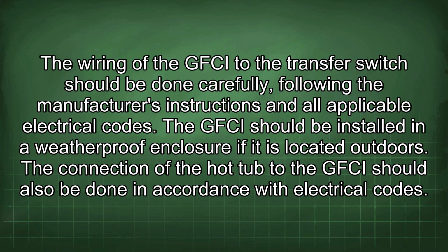The wiring of the GFCI to the transfer switch should be done carefully, following the manufacturer's instructions and all applicable electrical codes. The GFCI should be installed in a weatherproof enclosure if it is located outdoors.